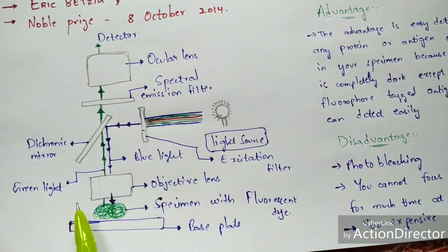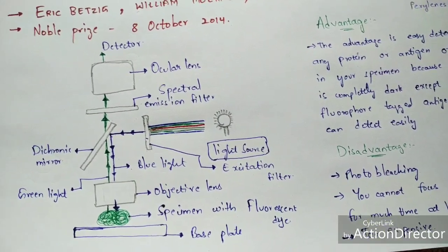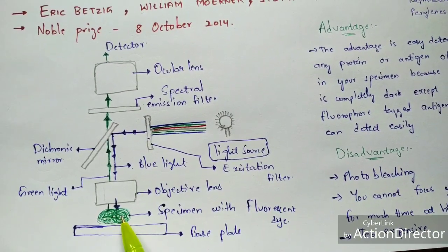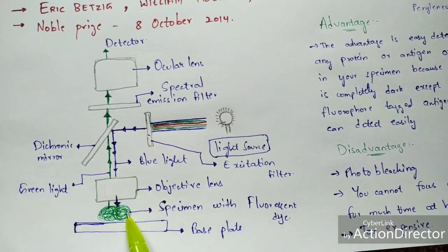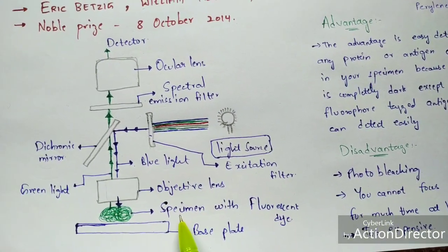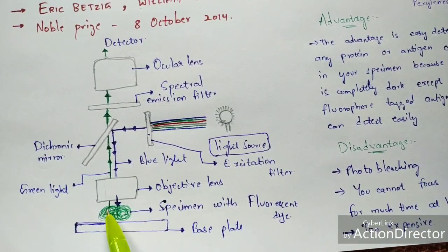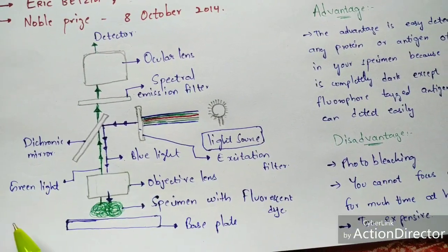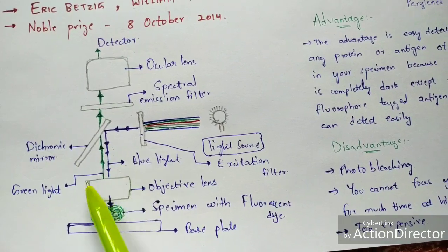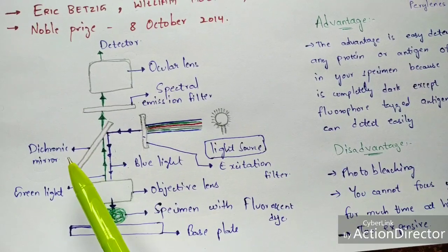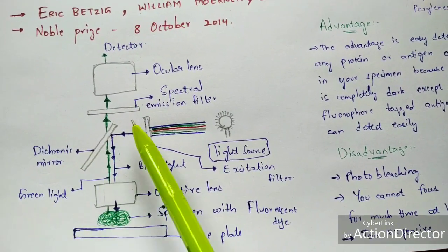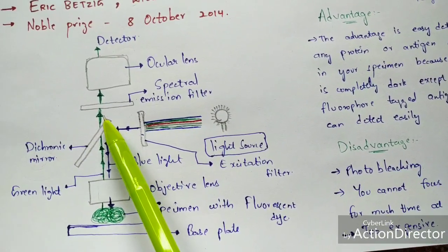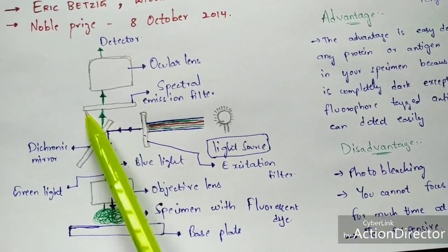The blue color light from the objective lens is allowed to fall upon the specimen. The specimen is mixed with a fluorescent dye, and major fluorescent dyes are green in color. So the specimen emits green color light. Along with the green light, blue color light also travels back through the objective lens to the dichroic mirror. The dichroic mirror rejects most of the blue color light, and the remaining green color light along with some residual blue light passes on to the spectral emission filter.